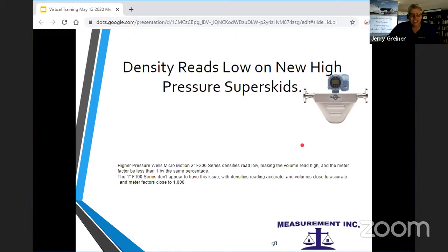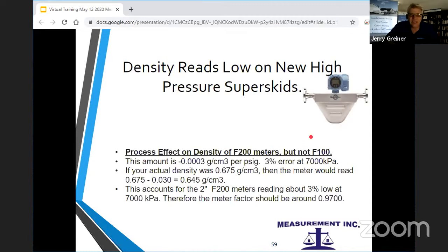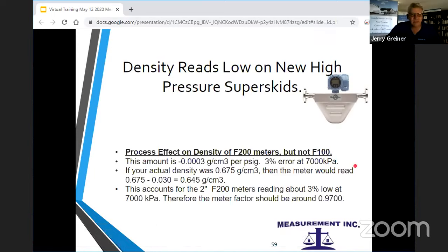On the 1-inch F series, which some of them use, the readings were accurate, the density was accurate, and the meter factors were really close to 1. What we found is there's a process effect on the density of the F200 meters, and not on the F100 or the different series of these. It only affects the 2-inch meters, at 0.0003 grams per cm3 per psig, which makes a 3% error at 7,000 kPa, around 1,000 pounds, and that's what these were running.